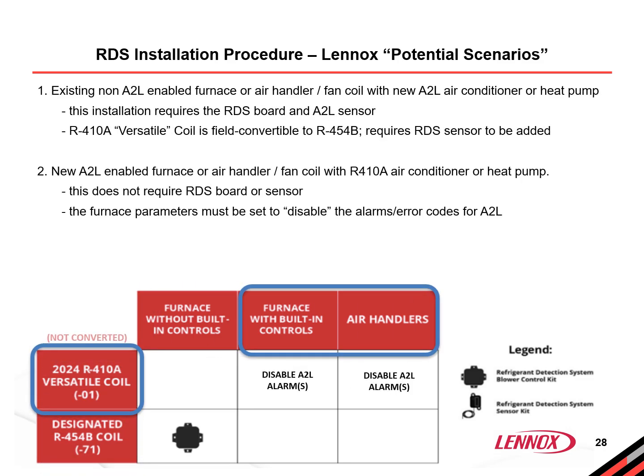In this second example, we have an A2L enabled furnace or air handler paired with a 410A system. This setup doesn't require an RDS board or sensor because there's no A2L refrigerant involved. However, it's important to update the furnace parameters. You'll need to disable the A2L specific alarms and error codes since they won't apply here. Follow each furnace manufacturer's installation guide for more specific setup details.